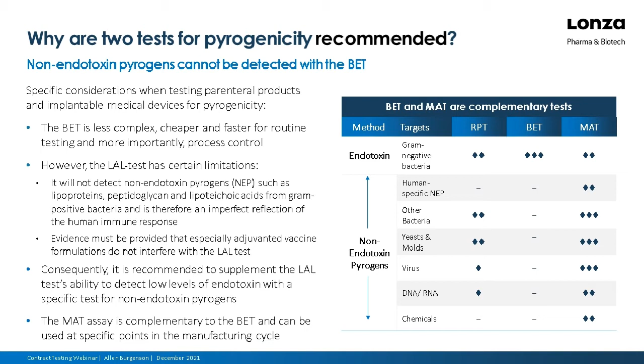Consequently, it's recommended to supplement the LAL test's ability to detect low levels of endotoxin with a specific test for non-endotoxin pyrogens. And the MAT assay is complementary to the BET and can be used at specific points in the manufacturing process. And as you can see in the graphic to the right, we have the method, endotoxin and non-endotoxin pyrogens, and the targets, and the number of diamonds indicates the level of suggestion for using that assay. So for endotoxin, the BET is highly recommended. But for other bacteria, the MAT is highly recommended. Also viruses and yeast and molds.